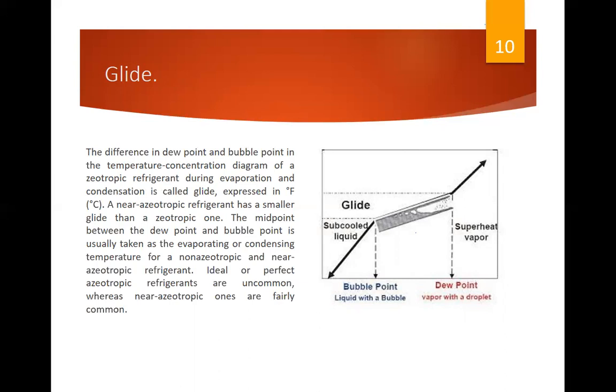A near azeotropic refrigerant has a smaller glide than zeotropic one. The midpoint between the dew point and the bubble point is usually taken as the evaporating or condensing temperature for non-azeotropic and near azeotropic refrigerant. Ideal or perfect azeotropic refrigerants are uncommon, whereas near azeotropic ones are fairly common.